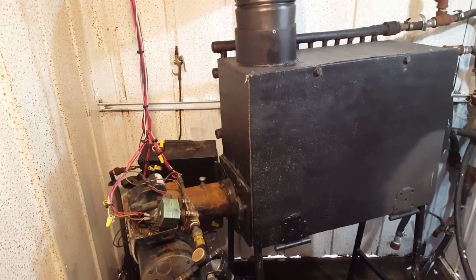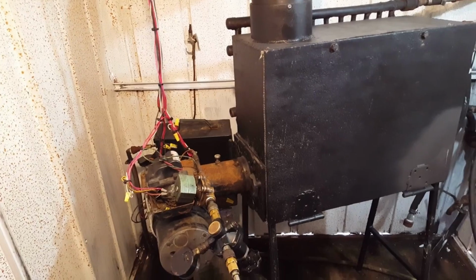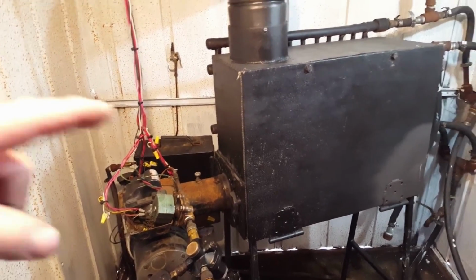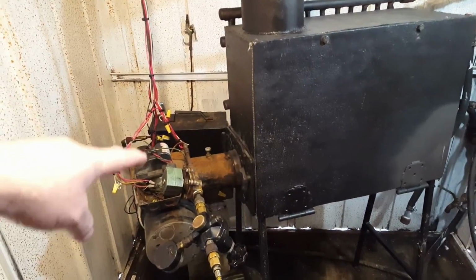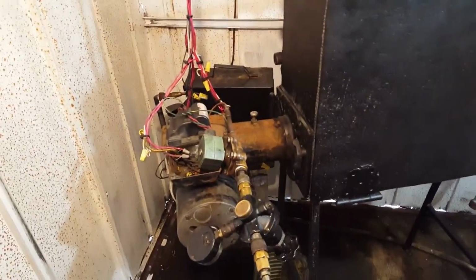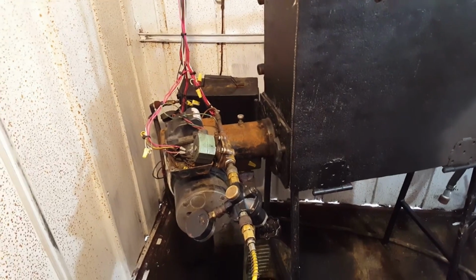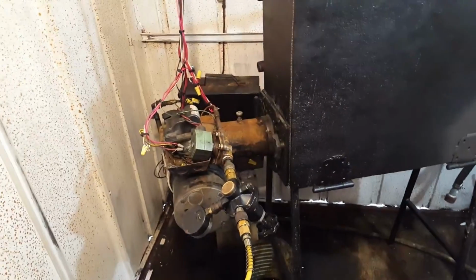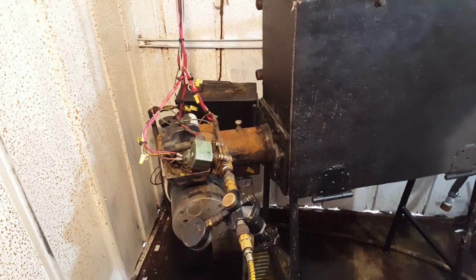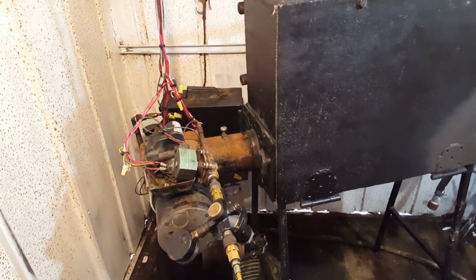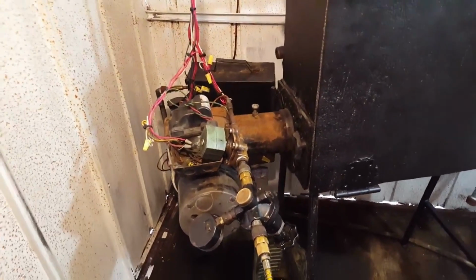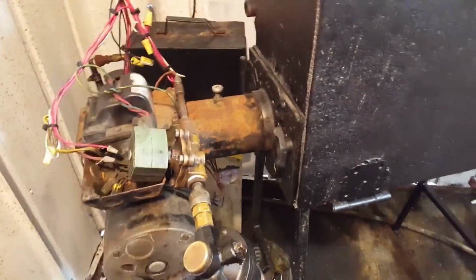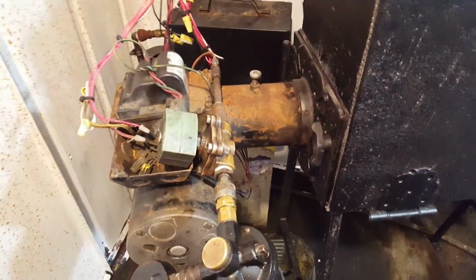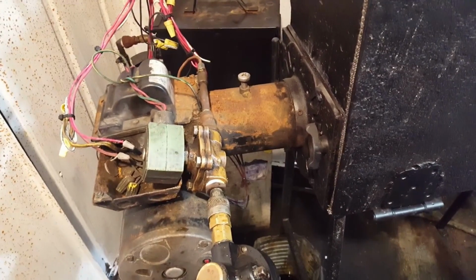When I set the building up here, I've got a jack in that corner over there. The reason for that is I want that burner tube going downhill. That way the oil dripping out of that burner won't accumulate in the end of the burner. It'll run on down the burner tube and hopefully won't set off that flame sensor when it's not supposed to be. But I have a lot of trouble out of that. It gives me a lot of trouble. That's usually what kicks this thing out, is that flame sensor sees that flame when it shouldn't.